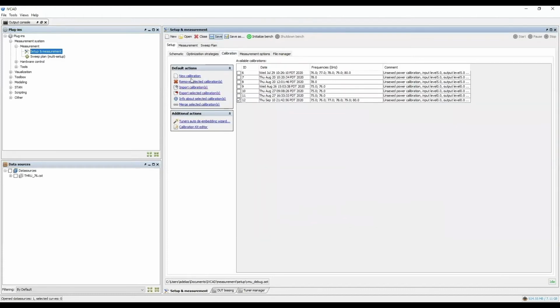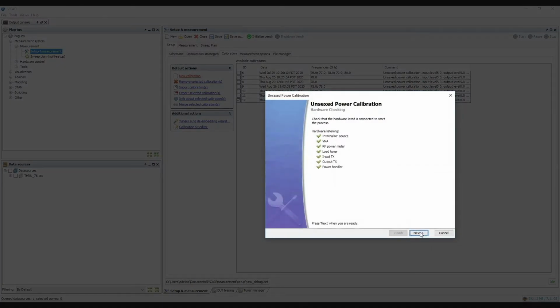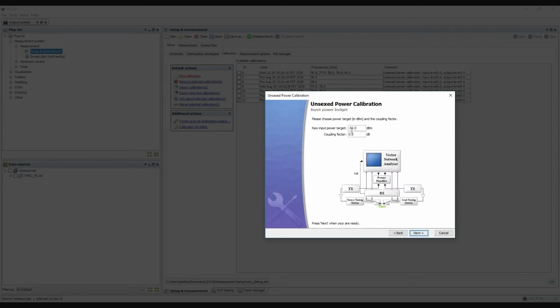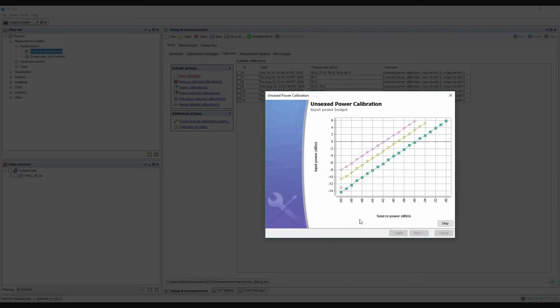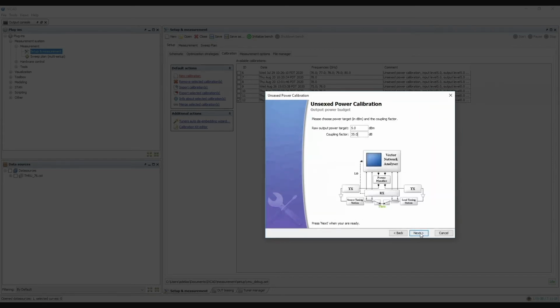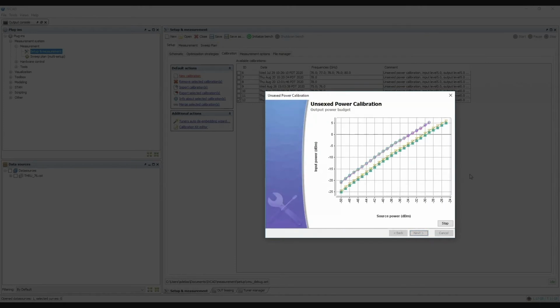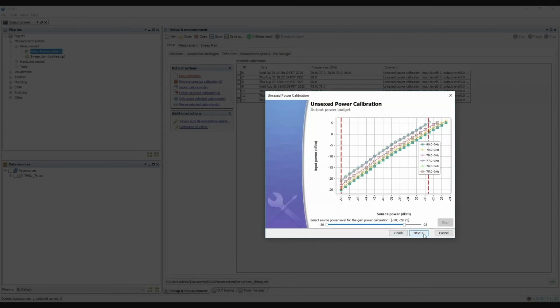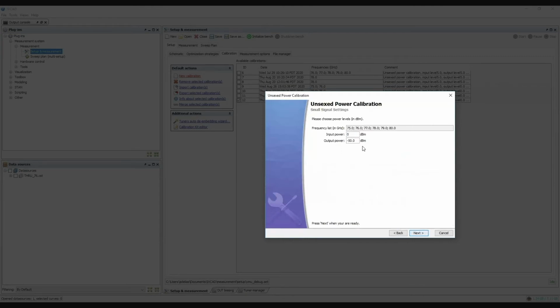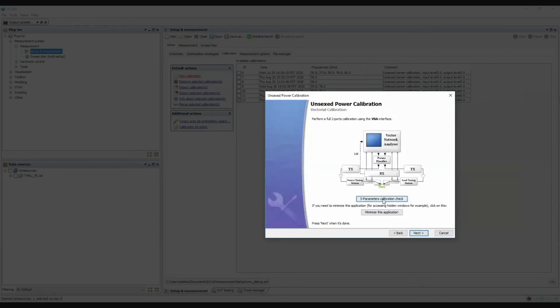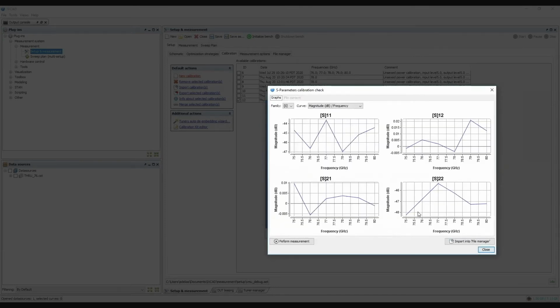We start the calibration by first performing a power gain characterization on the input network. This will enable the accurate available power control on the input of the DUT. Then we go through the same procedure on the output of the DUT. When we have successfully determined the gain of the input and output networks, we can perform the standard vector receiver calibration to establish the DUT measurement reference planes.